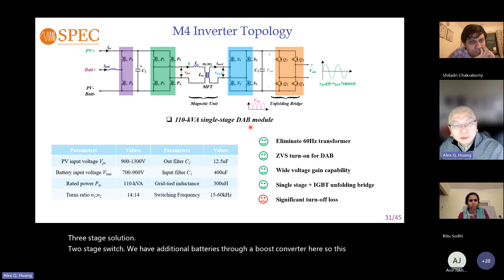We have additional batteries through boost converters here. This topology has each module at about 110 kilowatt. One key thing about the dual active bridge is ensuring its soft switching capability — even though silicon carbide is very efficient, we still want soft switching to improve efficiency, because silicon carbide is fast but not lossless.